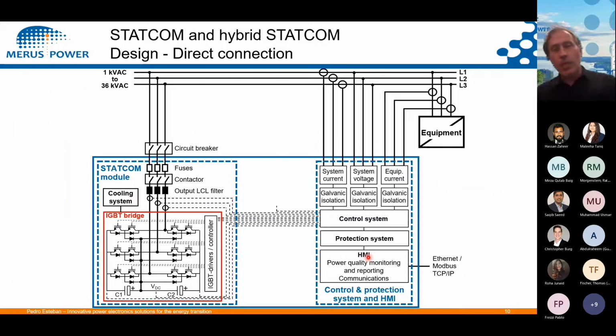How are they built? What is the design? As I mentioned before, depending on the manufacturer and the design, we can connect them directly into this voltage range up to 36 kV. An important thing to notice here is that they are connected in parallel with the equipment that generates the problems. So we need some measurements from the equipment and from the network, and the control system will be firing the IGBTs to inject into the system a certain current that will take care of the problems, or provide the ancillary services needed.